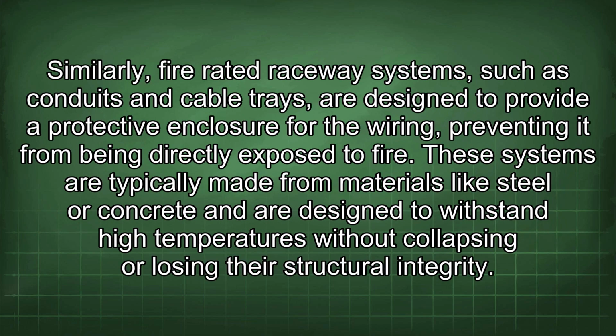Similarly, fire-rated raceway systems, such as conduits and cable trays, are designed to provide a protective enclosure for the wiring, preventing it from being directly exposed to fire. These systems are typically made from materials like steel or concrete and are designed to withstand high temperatures without collapsing or losing their structural integrity.